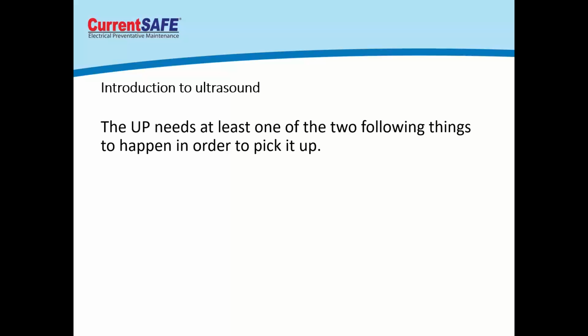The ultra probe really needs at least two things for us to hear anomalies. One is turbulent flow, so it's really good for early detection of leaks—in vacuum systems, air systems, pressurized fluid flows. The other thing it needs is friction, some kind of disturbance to pick up what that anomaly is doing. Those are the two things we need for ultrasonic detection to work.